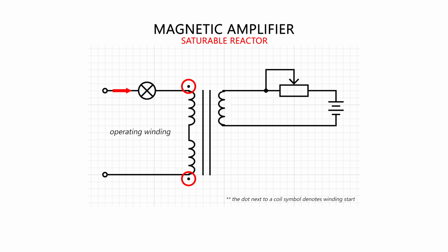The control current is supplied to the secondary or control winding. The primary operating winding contains relatively few turns. In its initial passive state, the magnetic flux it generates is insufficient to saturate the core. The load, the bulb, is thus de-energized, since most of the supply voltage drops across the reactance of the primary winding. The secondary control winding, however, contains a large number of turns.